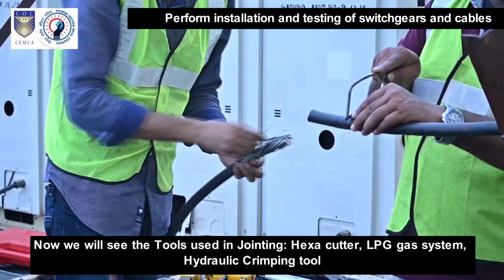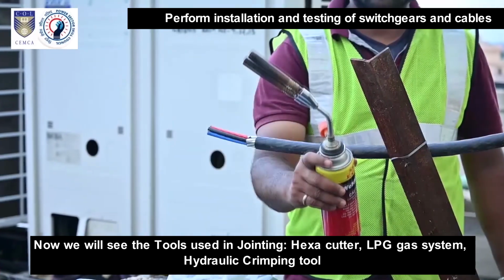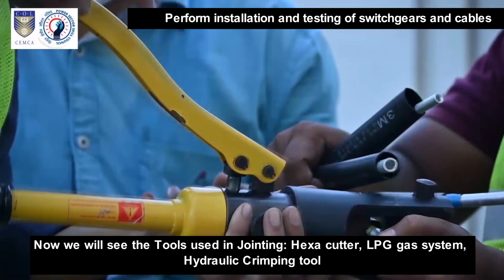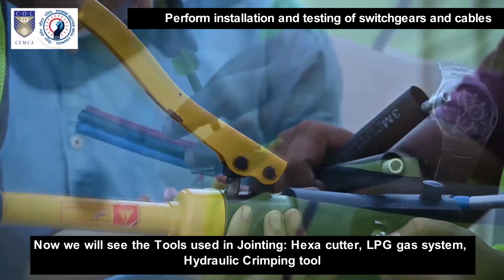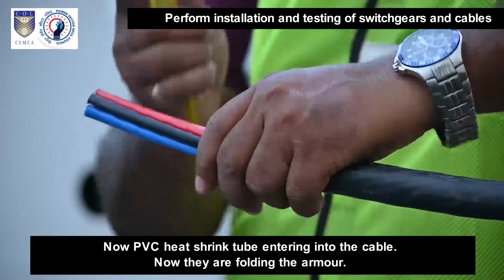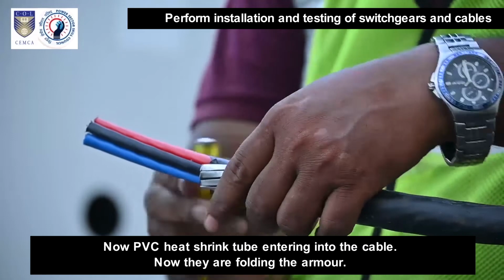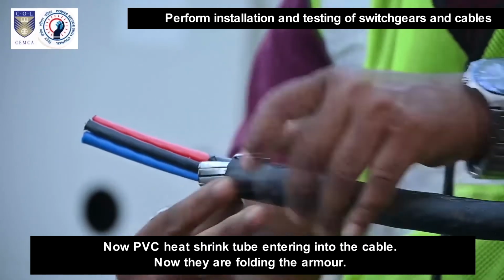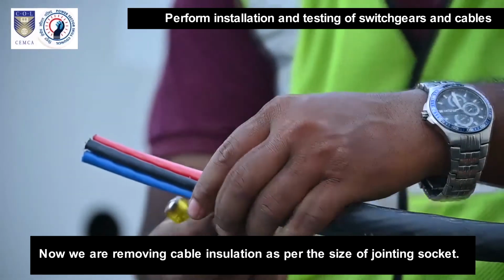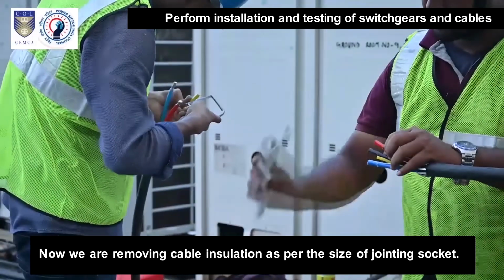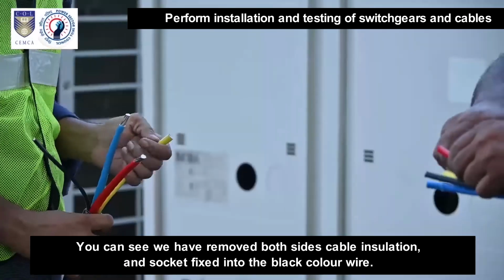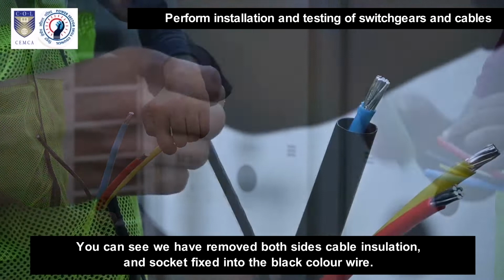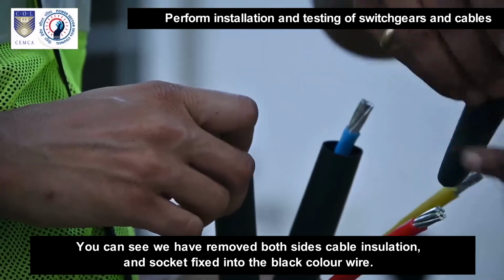Now we will see the tools used in jointing. 1. Hexa cutter. 2. LPG gas system. 3. Hydraulic crimping tool. Now the PVC heat shrink tube is entering the cable. Now they are folding the armor. Now we are removing cable insulation as per the size of the jointing socket. You can see we have removed both sides' cable insulation and the socket is fixed onto the black color wire.